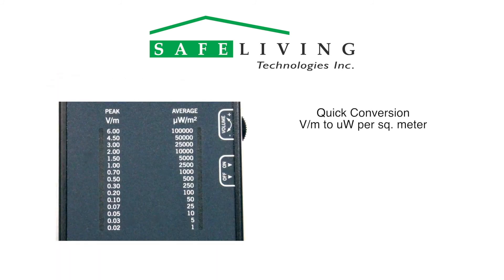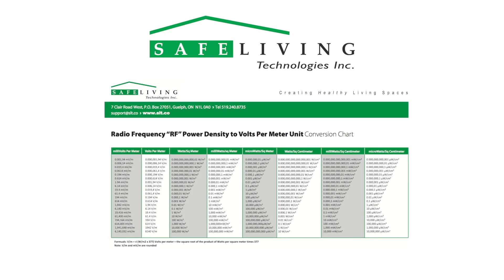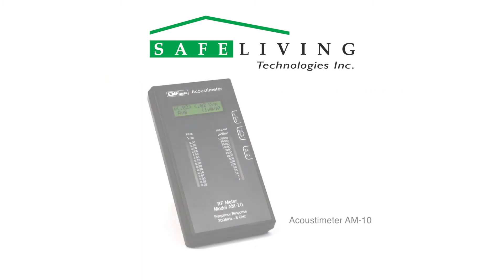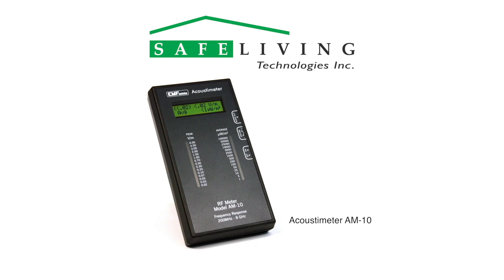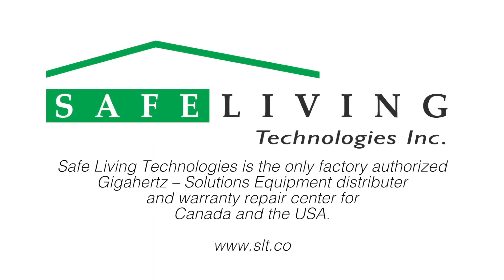The Acoustimeter's volts per meter peak scale can quickly be converted to microwatts per square meter by reading the corresponding value on the meter's scale to the right. For example, a peak reading of 0.7 volts per meter would equal a peak reading of 1,000 microwatts per square meter. You can also use the conversion table found on the Safe Living Technologies website to convert your readings to microwatts per square meter. For more detailed information about the Acoustimeter AM-10 and examples of common sound sources of microwave radiation, please visit the Safe Living Technologies website at slt.co.